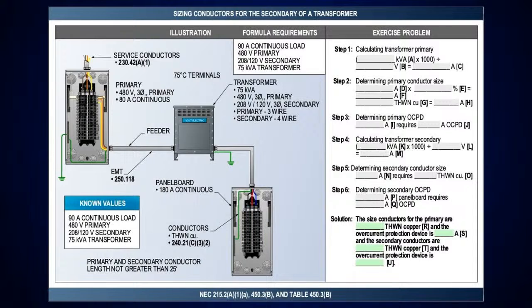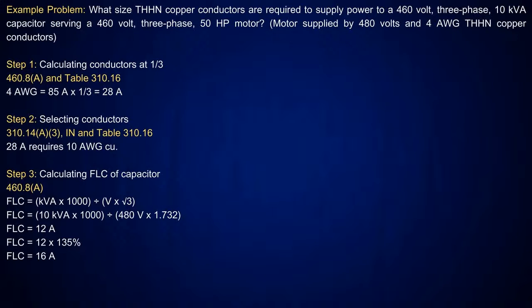And that's why I try to tell people the way you go about doing these calculations is really not that hard. It's just knowing I've got to get the amperage for the transformer, and I've got to get the amperage for the generator. Every one of those calculations is exactly the same. The only difference is if I had a generator, I had to put 115% on it. In this case, I had a continuous load, so I had to take it at 125%. So it depends on what you're looking at, but we try to cover every spectrum here so everybody knows where to find this information in order to perform this calculation correctly.